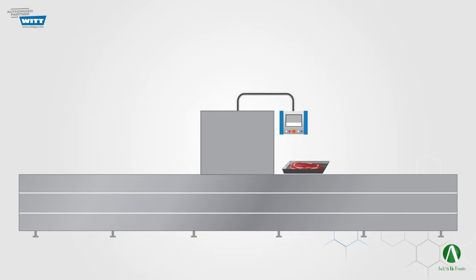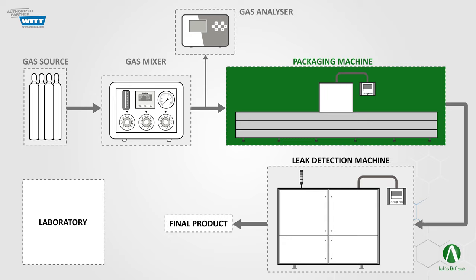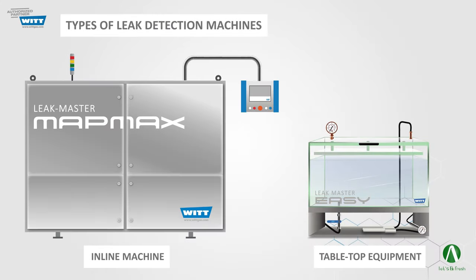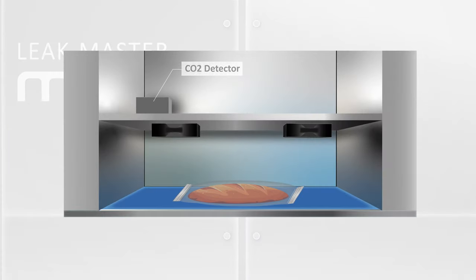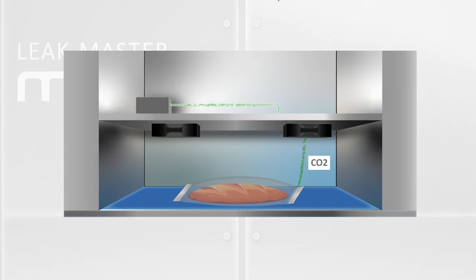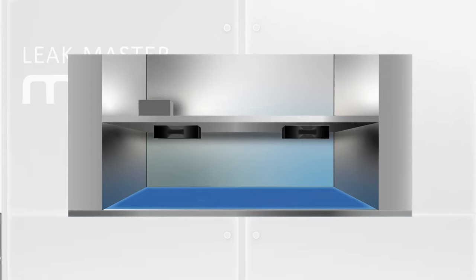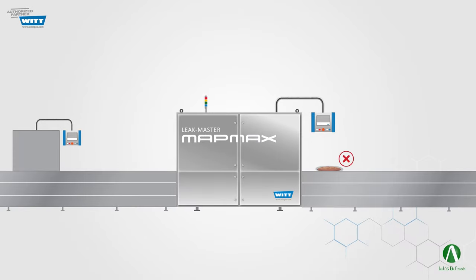But it is not the end. As our product quality will be dramatically affected by leakages, we have to be sure it is sealed properly. So the next stage is to make sure the product package is free from any leakages using a leak detection machine. Inline leak detection machines work with integrated high-technology sensors which detect trace gases like carbon dioxide. Since CO2 is already part of the modified atmosphere, it delivers the best results in terms of relevant leak size and is not expensive. Installed on the production line, they can detect even the smallest leaks in a fraction of a second when trace gases escape from the packages, and can also automatically remove the faulty packs from the production line.